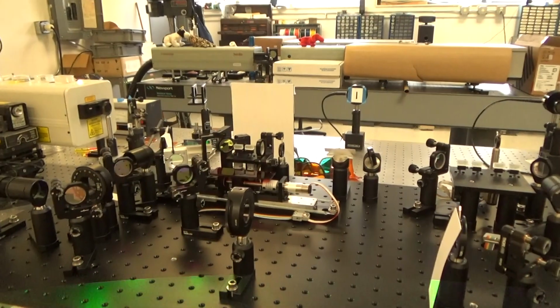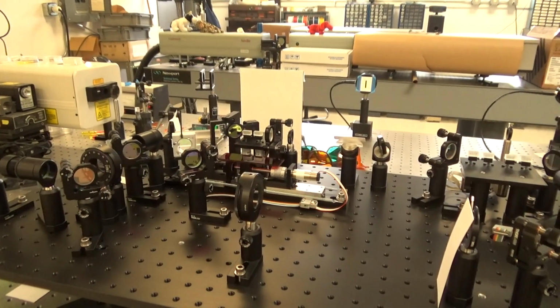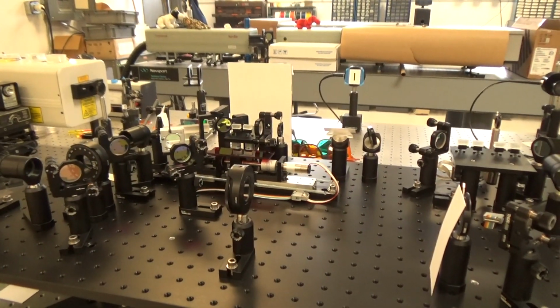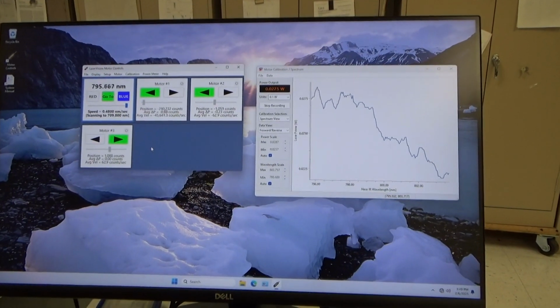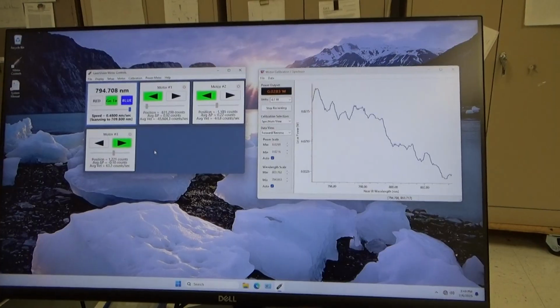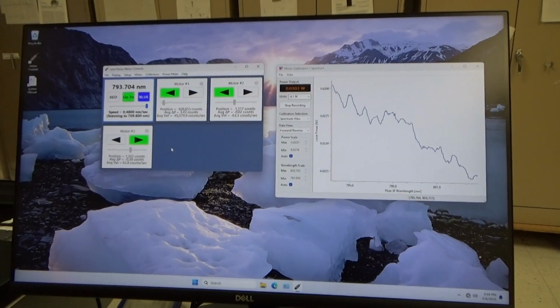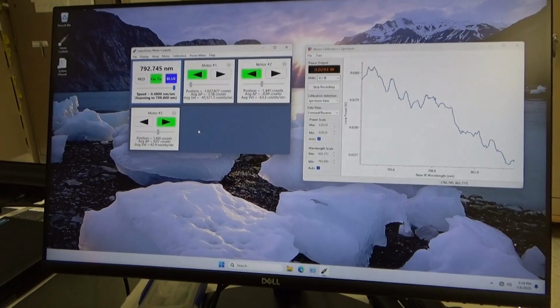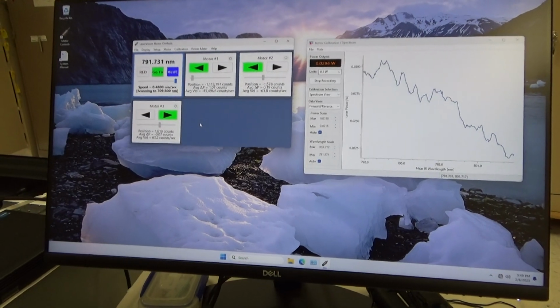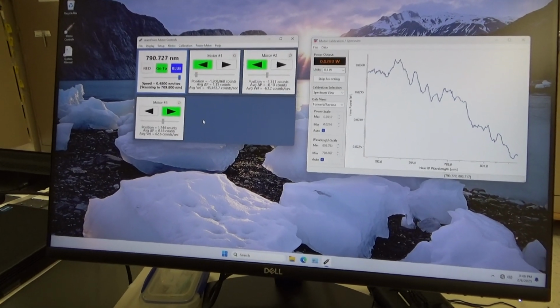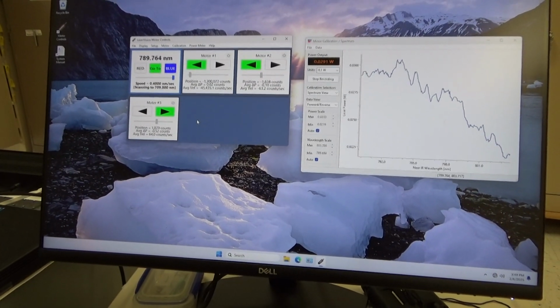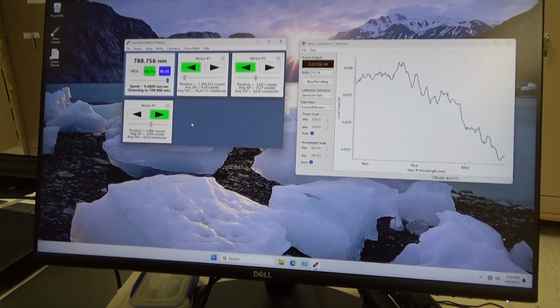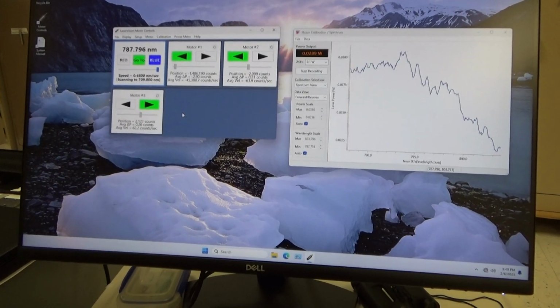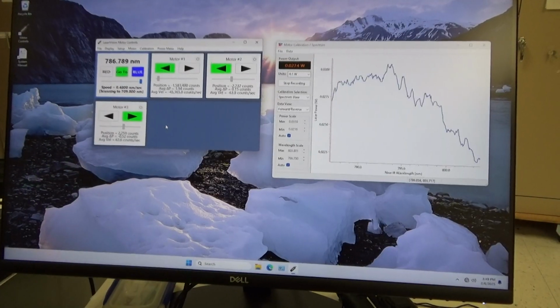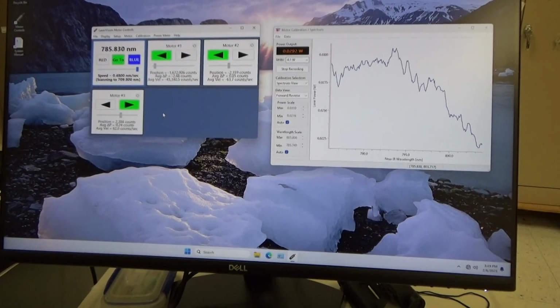For the most part, the earlier calibration that I'm using for the system should be very close, and so I shouldn't see a significant fall off in power. But if I do, what I would do is stop the scan, re-optimize motor number 3 in broadband mode, and then re-optimize motor number 1 in narrowband mode, and then continue on down to 710 so I can begin the calibration run.